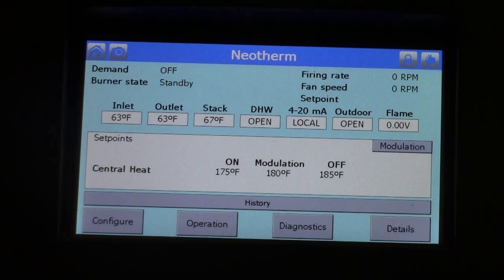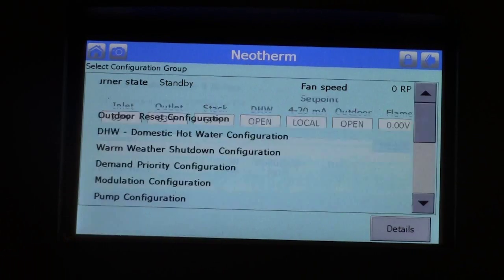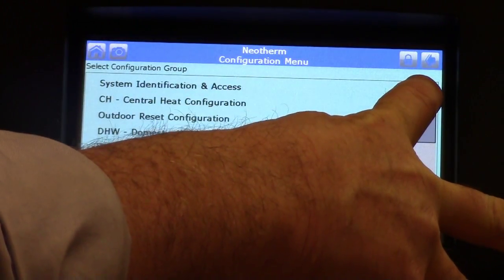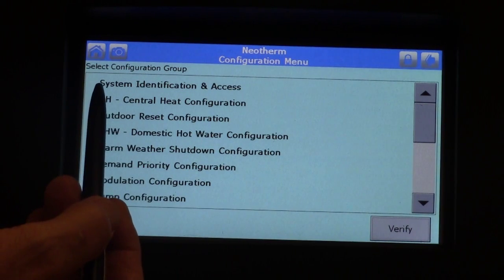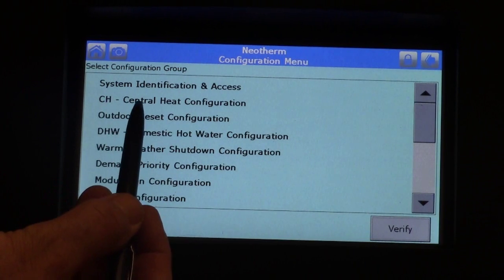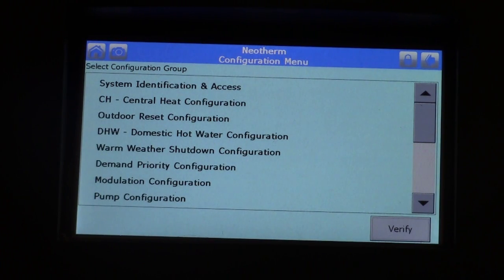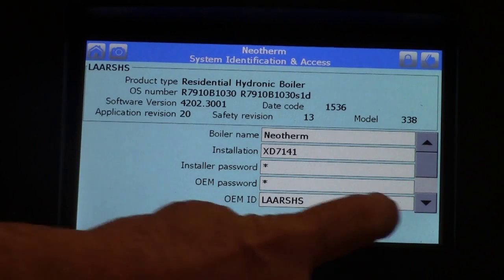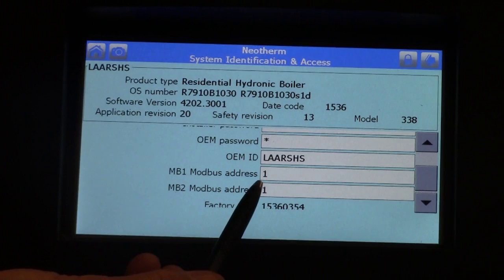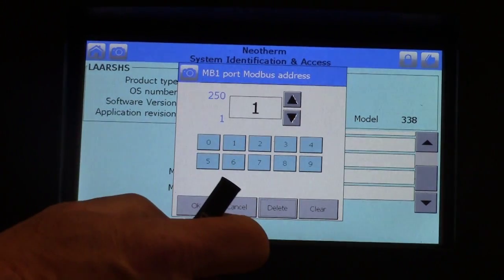We're going to set the boiler up as a stand-alone single boiler application. To get there, click configure. We have a few line items up top and a slide rail on the side — there are many options in here. However, for a single boiler, we're only going to use the first five lines: system identification and access, central heat, set points, outdoor reset, DHW (domestic hot water), and warm weather shutdown. Start with system ID and access — click on that, use your slide rail, scroll down, and the Modbus addresses here should both read one. If they don't, click on them and change the address back to one.